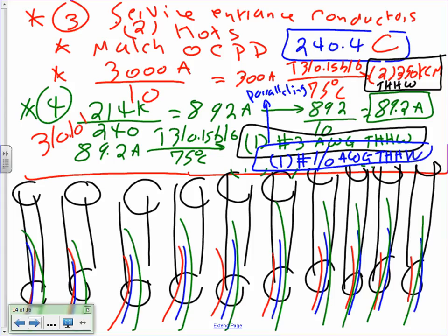Can you guys write this reference down? 310.10H. If you go to 310.10H, it tells you 1 aught is the minimum that you can parallel for any conductor, hot or not hot. That's new, this NEC code. It was really nothing new, but they shifted it, they rearranged it.